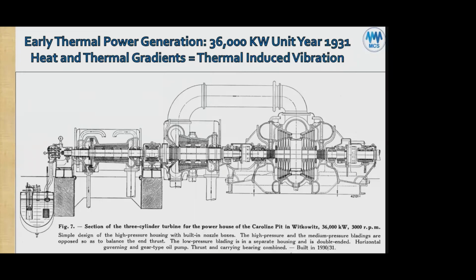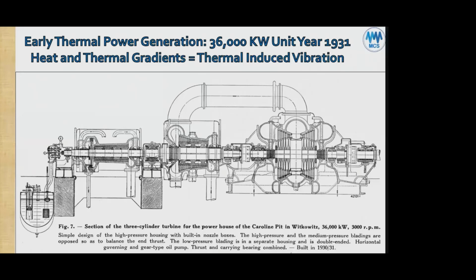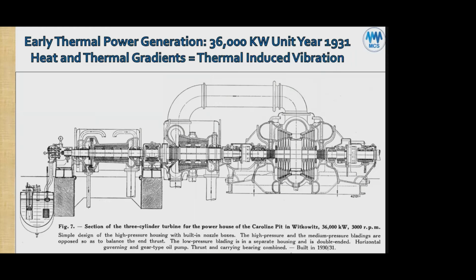What is the main cause of the sub-synchronous frequency at 0.4x for a turbine with tilting pad bearings, only at no load full speed condition, with the vibration level at 0.4x at no load condition about 80 micron? It could be multiple issues. Number one, something could be exciting the first critical. If the 0.4x is the actual first critical speed of the machine, something is exciting it, like a light rub. So he should, number one, search for a light rub and confirm that the 0.4x is actually the first critical speed of the rotor.